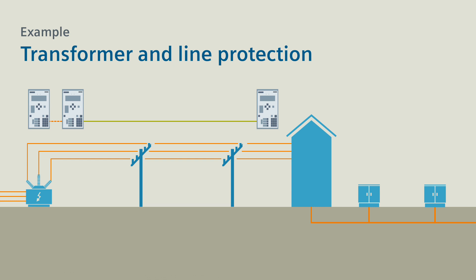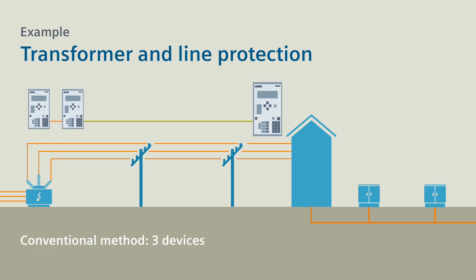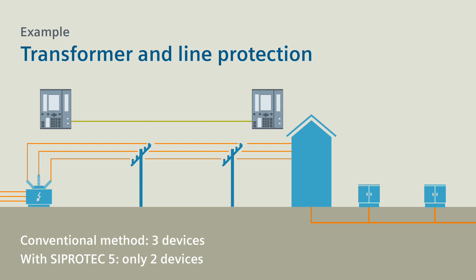Transformer and line protection. The conventional method requires one protection device for the transformer and one protection device each for the two line ends. SIPROTEC 5 is clearly the more efficient choice: instead of three devices, you now only need two. Transformer protection and line differential protection communicate via the protection data interface for this solution.